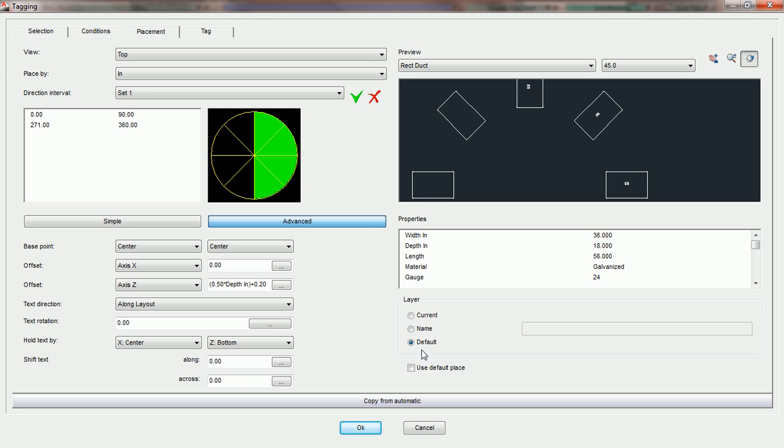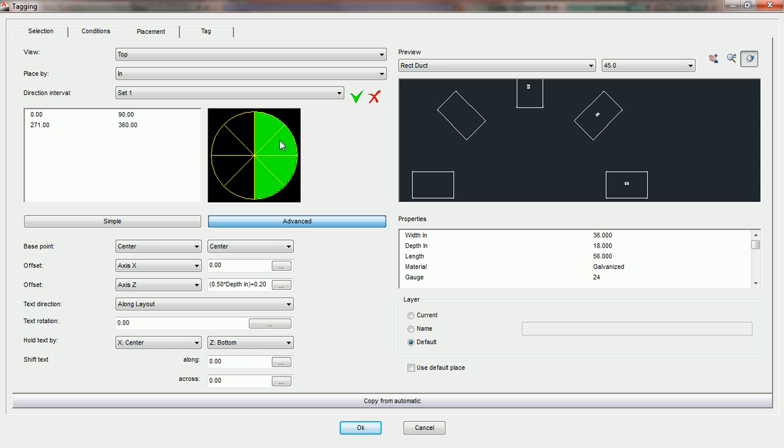If duct is going to be going up or down in a riser so that it's in an elevation view, you would notice that all the parameters in this particular section do not apply to that duct because we base everything on the X, Y, and Z axes in terms of direction intervals. There is no direction interval for duct that's going straight up. We only have it for all the intervals in plan view.